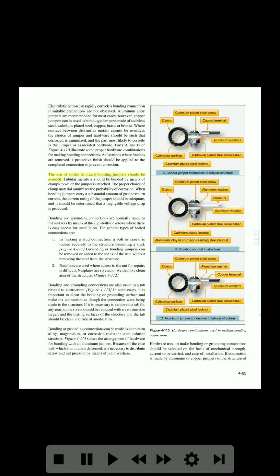The use of solder to attach bonding jumpers should be avoided. Tubular members should be bonded by means of clamps to which the jumper is attached. The proper choice of clamp material minimizes the probability of corrosion. When bonding jumpers carry a substantial amount of ground return current, the current rating of the jumper should be adequate, and it should be determined that a negligible voltage drop is produced.